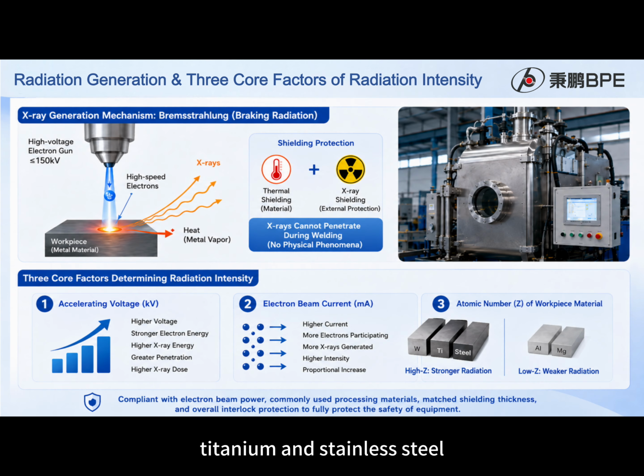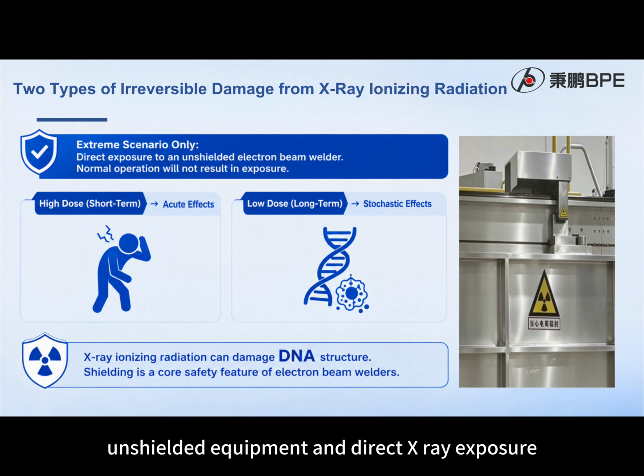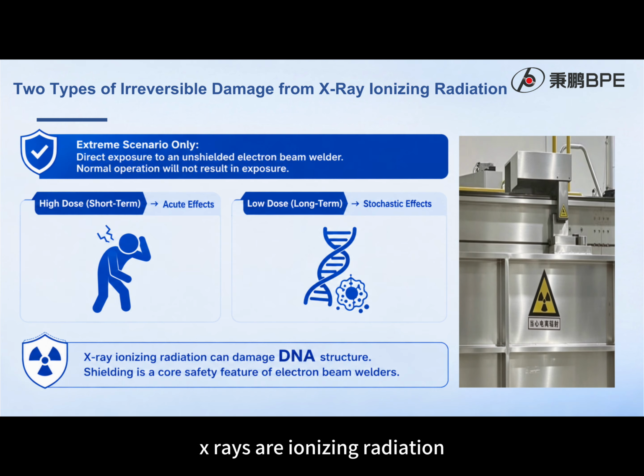The effects discussed here apply only to extreme conditions involving completely unshielded equipment and direct X-ray exposure. They do not occur during normal operation of properly shielded equipment. X-rays are ionizing radiation capable of damaging cellular DNA. High-dose exposure may cause acute radiation sickness, while long-term exposure above permissible limits may increase the risk of cellular and genetic damage. Therefore, reliable radiation shielding is an essential safety feature of electron beam welding equipment.